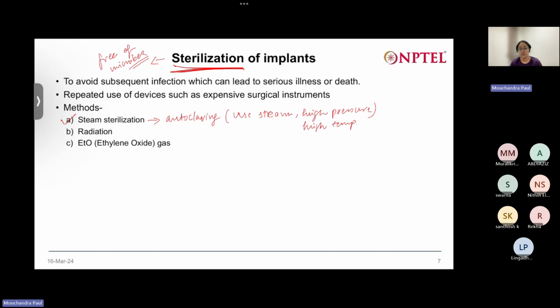Now there are various types of autoclaving, short cycle, long cycle autoclaving. The standard one that we do is we use 15 psi pressure and a temperature of 121 degrees Celsius, okay, to sterilize everything that comes in contact with our cells. So that is one method, steam sterilization, also called autoclaving.